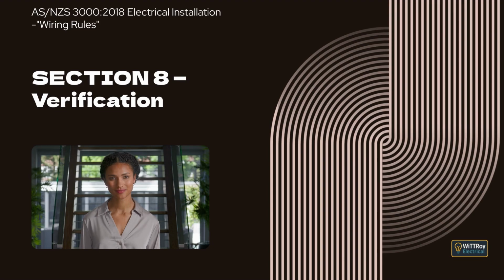Clause 8.3.5.2 Results. This clause explains that the resistance of protective earthing conductors must be low enough to allow sufficient current to flow to operate overcurrent protective devices, and consistent with the length, cross-sectional area, and type of conductor material. It also states that the resistance of the main earthing conductor or any equipotential bonding conductor must not exceed 0.5 ohms, with notes explaining how resistance values relate to protective devices and circuit characteristics.